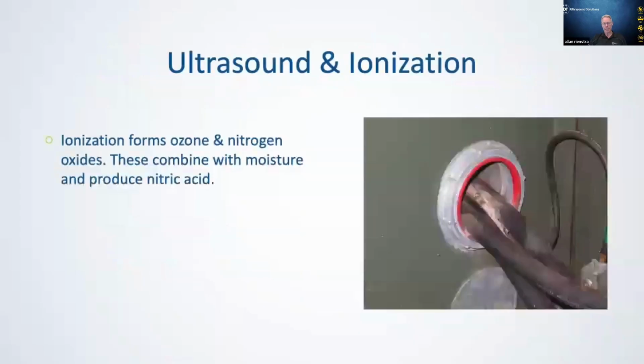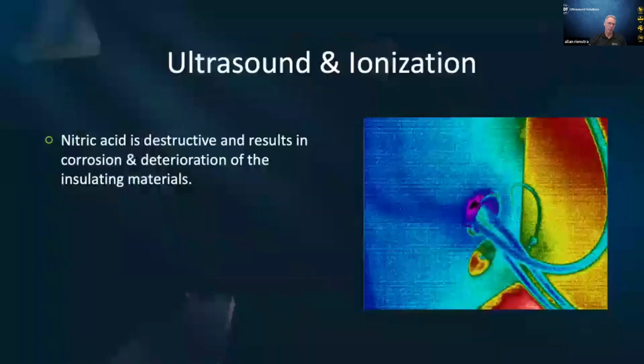So how does ultrasound detect? Well, what happens when we have a breakdown in the insulation material is at the source of, and I'll call it a leak, it's not a compressed air leak, but it's still a leakage. And at the source of that breakdown or that leakage, we have ionization. And the ionization forms both ozone and nitrogen oxides. And between the two of these, they combine with the moisture and produce nitric acid. Nitric acid is destructive, and it results in the corrosion and deterioration of the insulating materials.